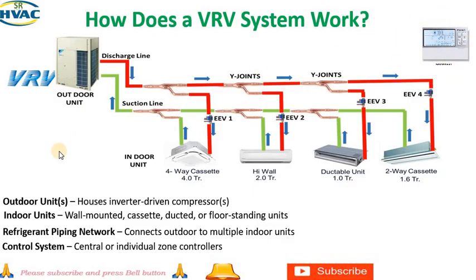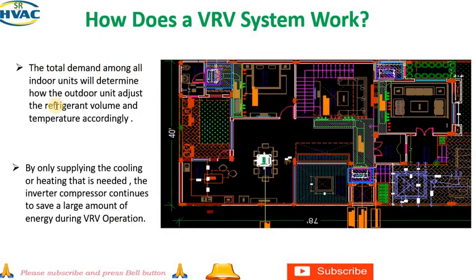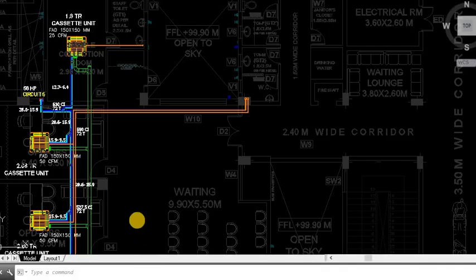Friends, the Daikin VRV system or any other VRV system works on how much demand or required temperature is to be set in a particular zone. Okay, see, the total demand of all the indoor units will determine how the outdoor unit adjusts the refrigerant volume and set temperature accordingly. By only supplying the cooling or heating that's needed, the inverter compressor continues to save a large amount of energy during VRV operation. Let's see one more example, friends.